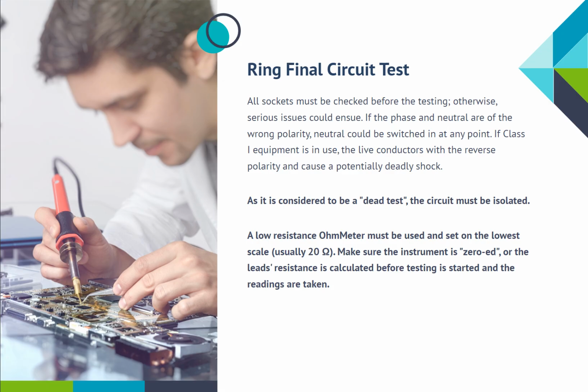A low resistance ohm meter must be used and set on the lowest scale, usually 20 ohms. Make sure the instrument is zeroed, or the leads' resistance is calculated, before testing is started and the readings are taken.